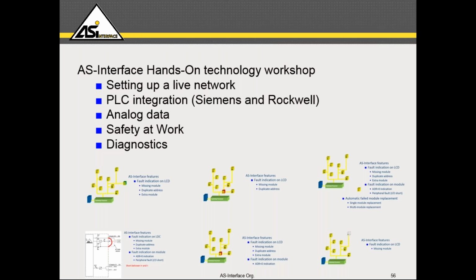We also do the PLC integration, just like what I showed you in a solution slide. We communicate an AS-i master monitor with a Siemens PLC. Also, we do communication to the higher level PLC with Rockwell PLC with the AS-i master monitor. At the same time, we talk about analog data, safety at work, as well as diagnostics information, how to diagnose a problem in the AS-i network. So we talk about all that.